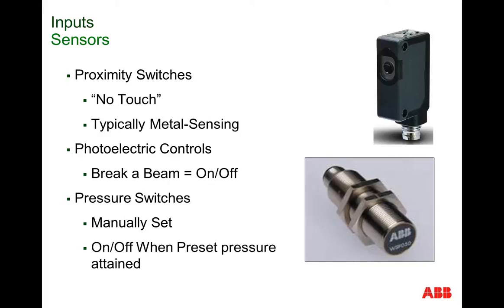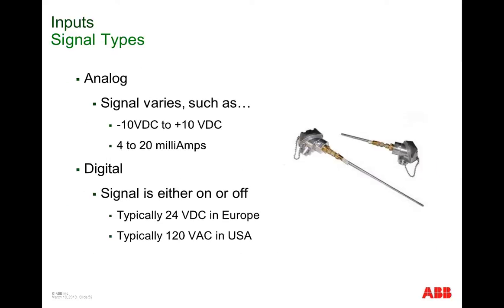Photo eyes and proximity sensors provide the absence and presence detection of a limit switch, but they're no touch by design. A product either breaks a light beam, or in the case of a proximity device, it'll detect a piece of metal coming within a few millimeters of the sensing head of the prox, and that's the little cylinder device shown in the bottom right. No touch means less mechanical wear, and therefore less machine downtime.